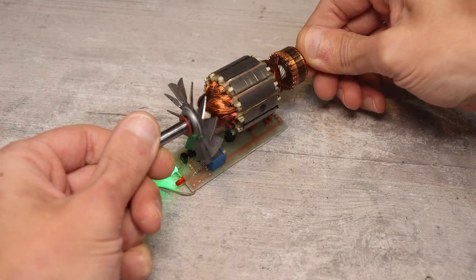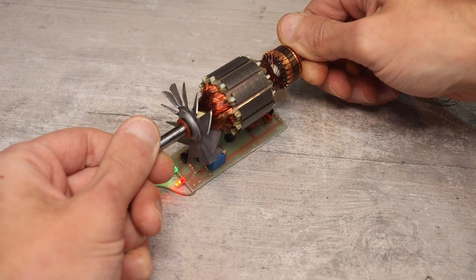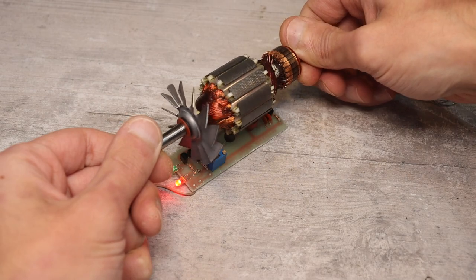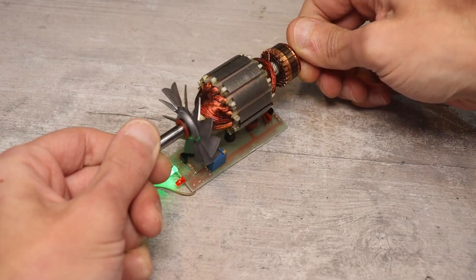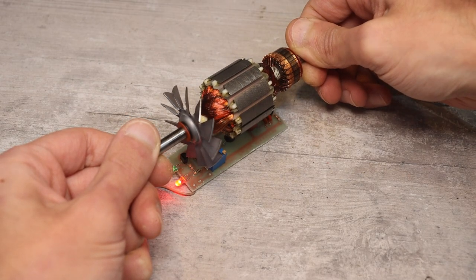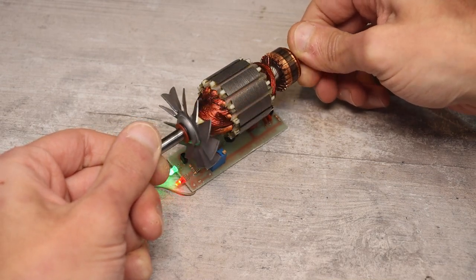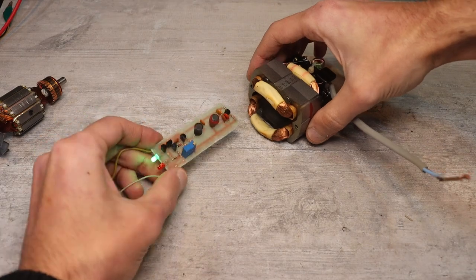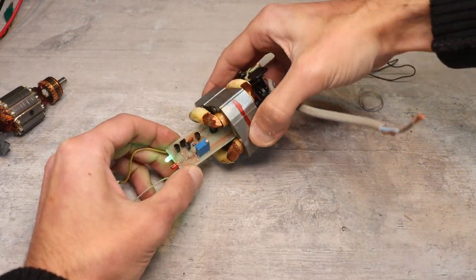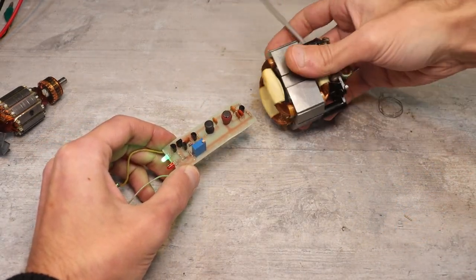The device works like this. Bring the coil of the detector, for example, to the rotor of the electric motor, and rotate it. Or you can move the detector itself. If there are short-circuited turns in a certain place, the red LED will light up. If there is no short circuit, the green indicator will light up.